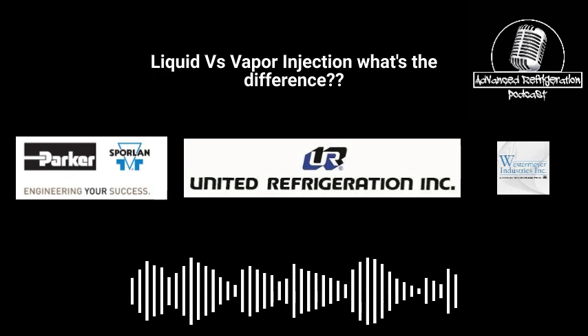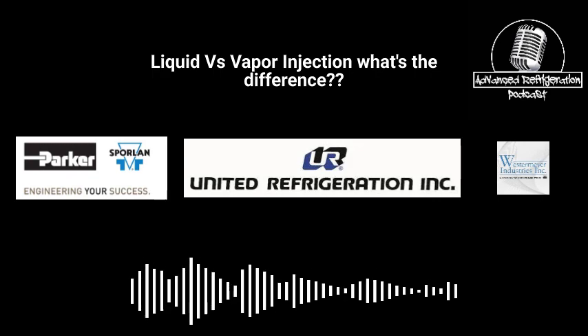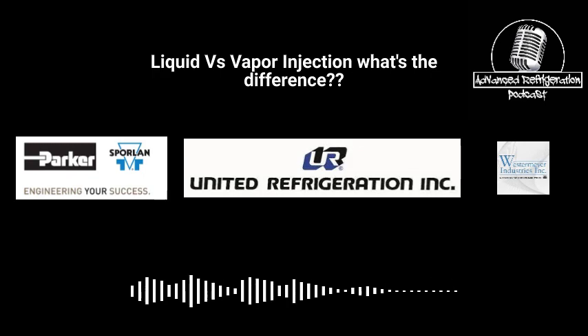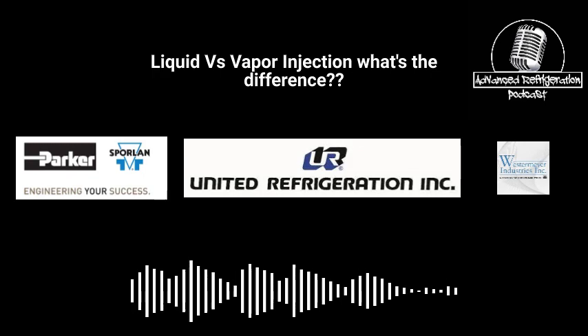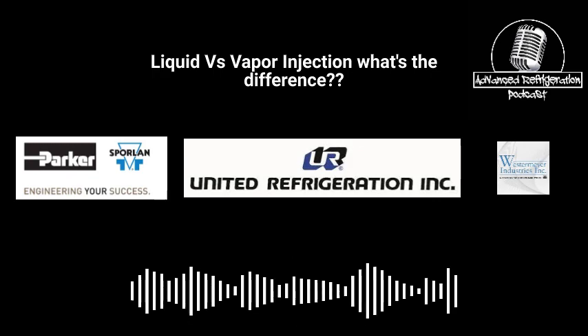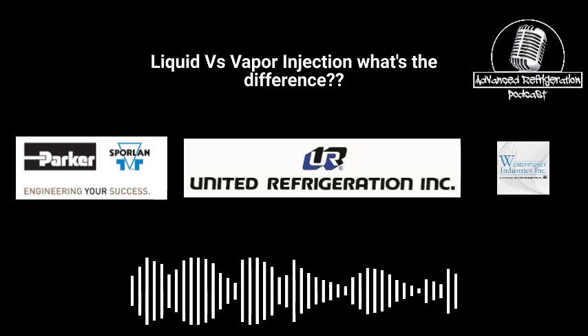I've seen where the solenoids are just old and not opening all the way. If you check the pressure before and after the EPR, they'll be the same pressure, but it'll be elevated. It'll be like 60 or 75 degrees saturated instead of the 35 or 45 that you're trying to maintain. And when I forced the solenoid stem in, you actually saw the pressure start to come down. So that would be one reason you could potentially cause a whole bunch of liquid to go into those compressors.